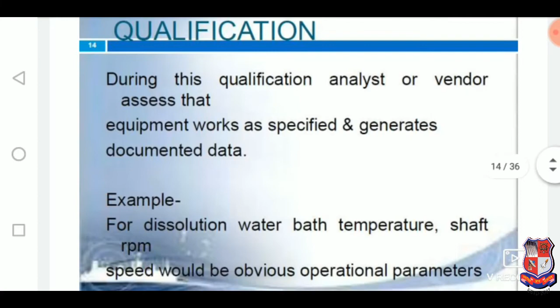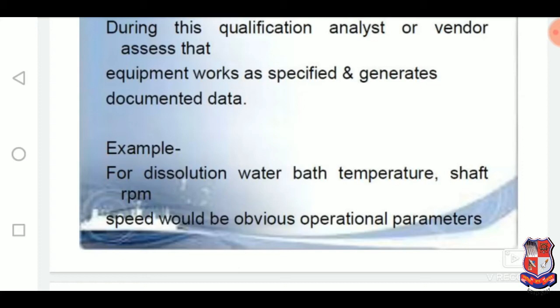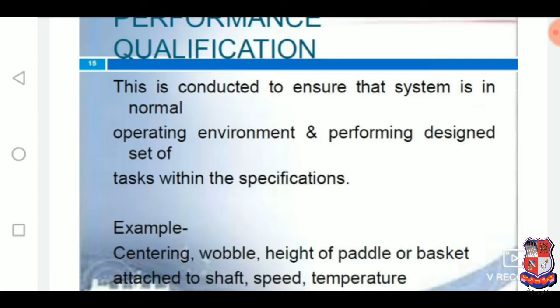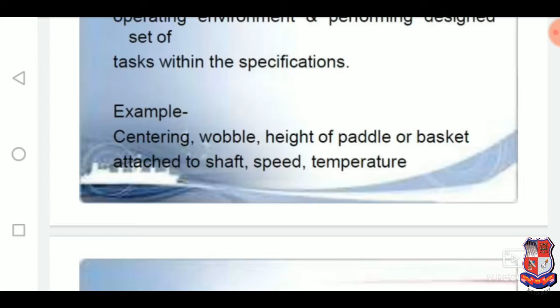During this qualification, the analyst or vendor assesses that the equipment works as specified and generates documented data. For example, temperature, shaft RPM, and speed would be obvious operating parameters. After that, performance is assessed, in that the system is in its normal operating environment, performing designed tasks within the specification. For example, centering, wobble, height of the paddle or basket attached to the shaft, speed, and temperature.